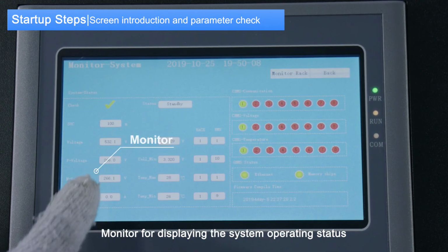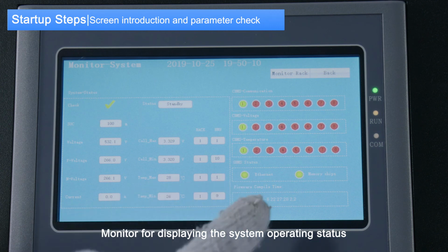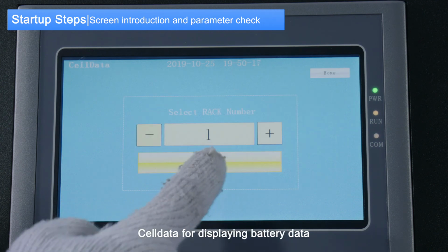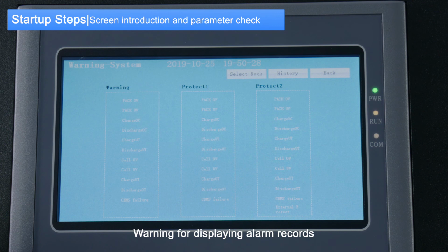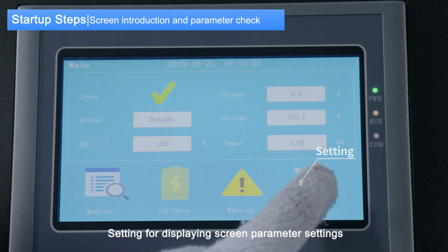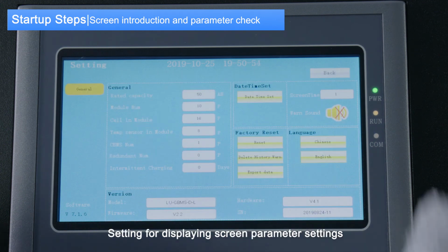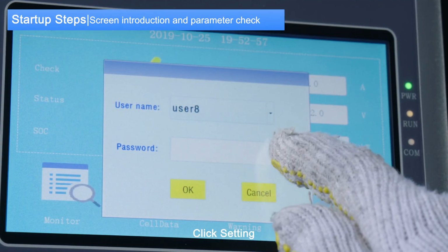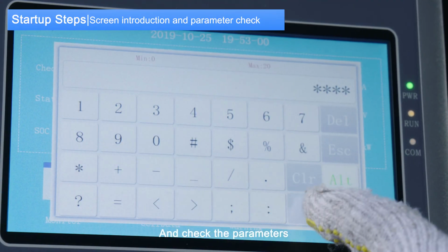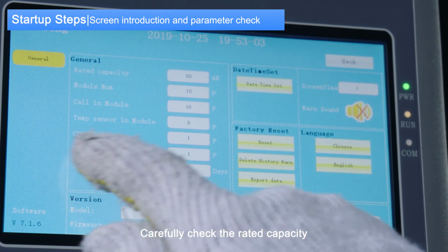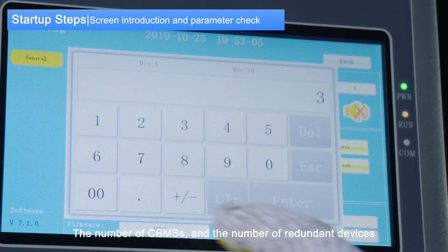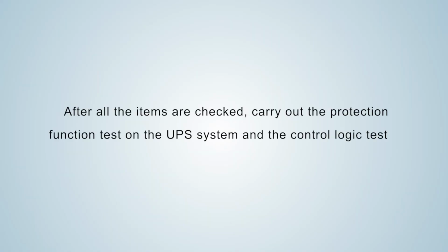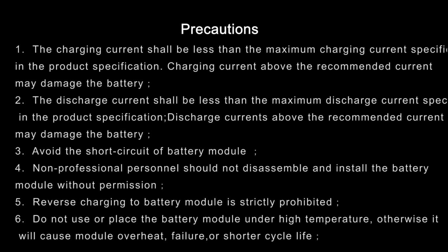Monitor for displaying the system operating status. Cell data for displaying battery data. Warning for display alarm records. And setting for displaying screen parameter settings. 2. Click Setting. Log into the system and check the parameters. Carefully check the rated capacity, the number of CBMSs, and the number of redundant devices. After all the items are checked, carry out the protection function test on the UPS system and the control logic test. 7. Precautions.